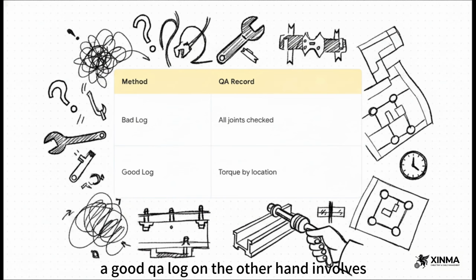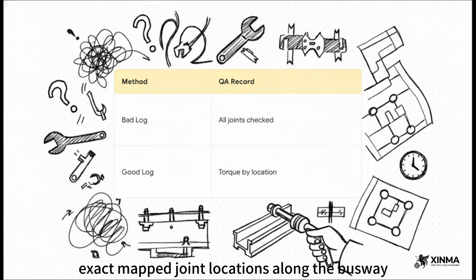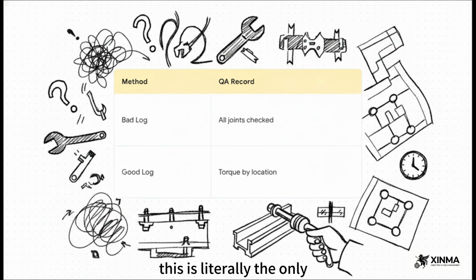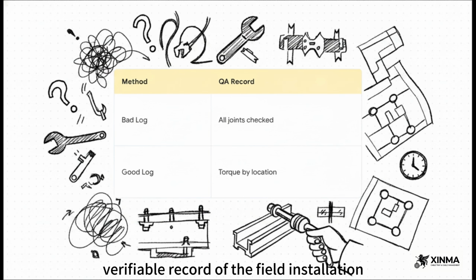A good QA log, on the other hand, involves specific location-by-location torque recording. You aren't just saying, yeah, I checked the joints. You are recording the exact torque applied at exact mapped joint locations along the busway. This is literally the only acceptable quality assurance method because it creates a permanent, verifiable record of the field installation.